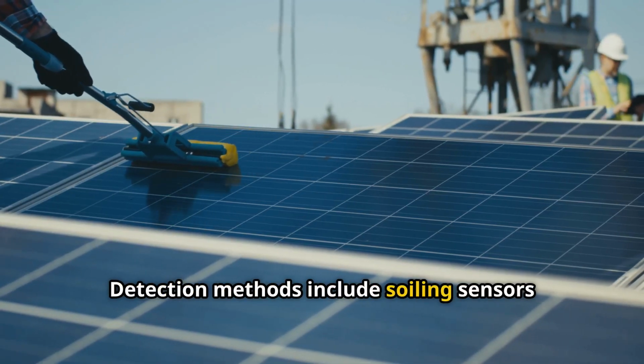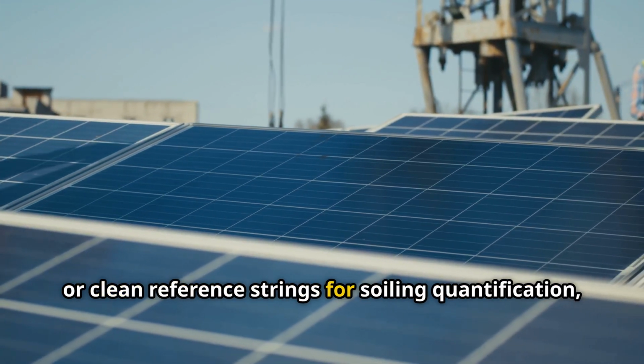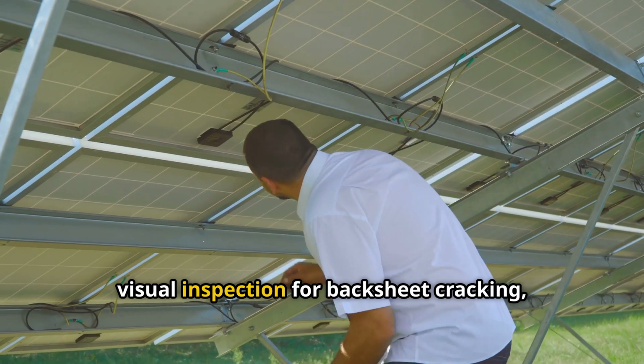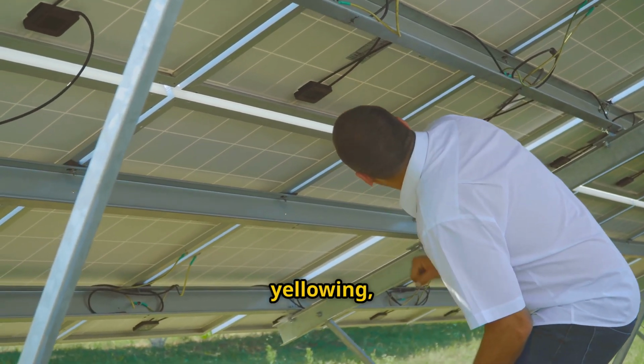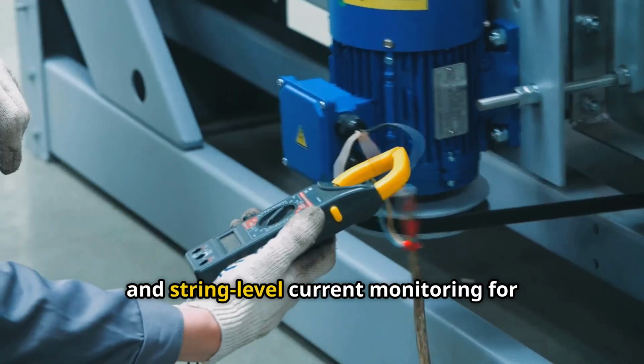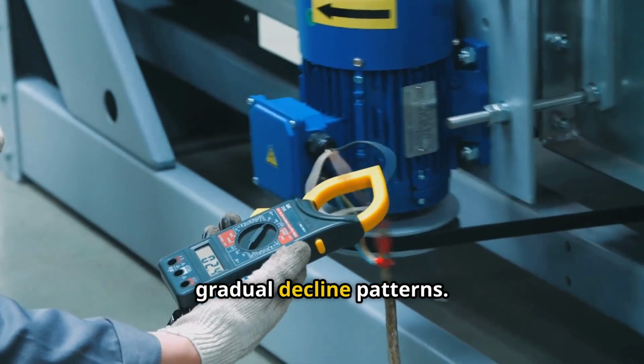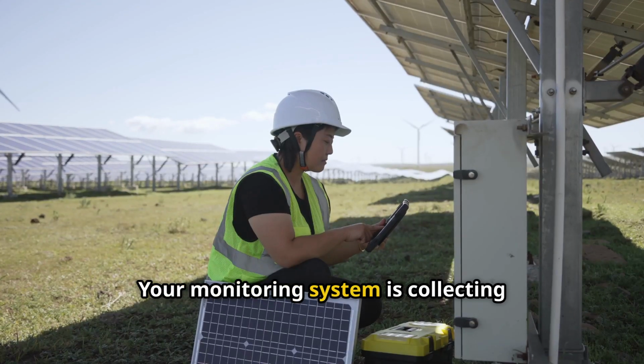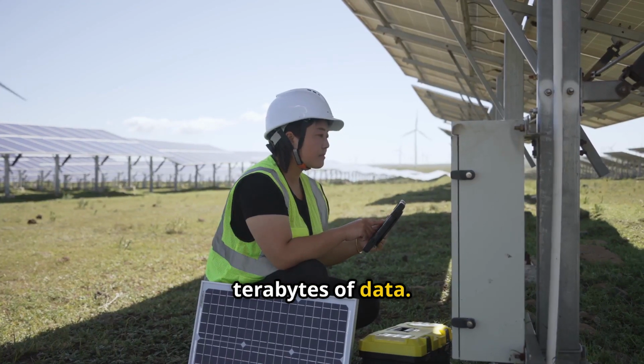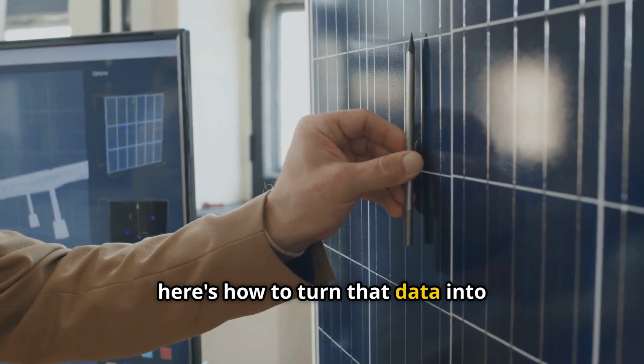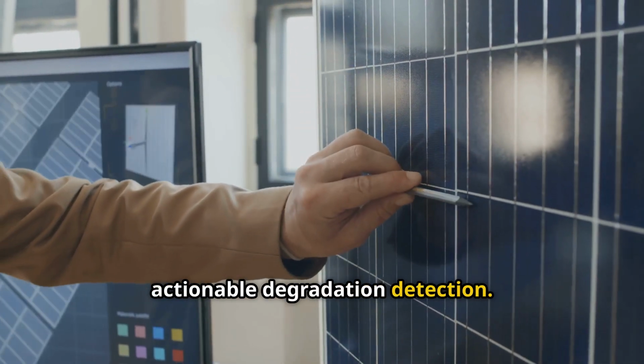Detection methods include soiling sensors or clean reference strings for soiling quantification, visual inspection for backsheet cracking, yellowing or delamination, and string-level current monitoring for gradual decline patterns. Your monitoring system is collecting terabytes of data. So, here's how to turn that data into actionable degradation detection.